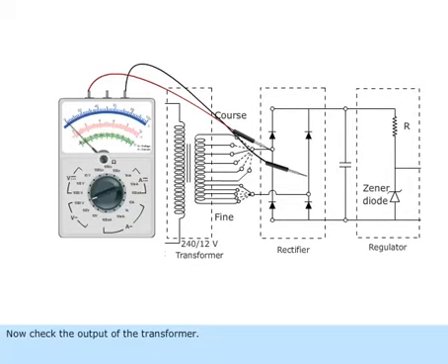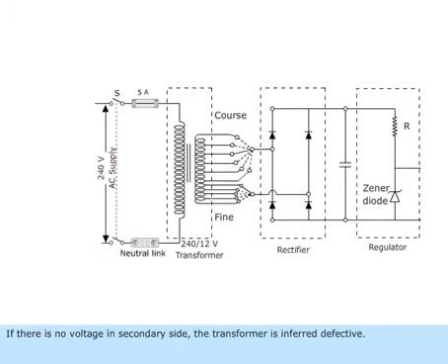Now check the output of the transformer. If there is no voltage in the secondary side, the transformer is therefore defective. Replace the transformer.